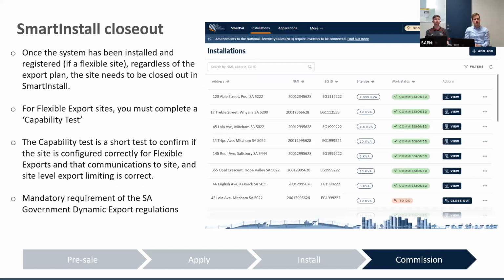So Smart Install Closeout. Once the system has been installed and registered if it's a flexible site, regardless of the export plan, the site needs to be closed out in Smart Install. The difference for flexible export sites is you must now complete a capability test. The capability test is a short test to confirm if the site is configured correctly for flexible exports and that communications to site and the site level export limiting is correct. It is also a mandatory requirement of the SA government dynamic export regulations.